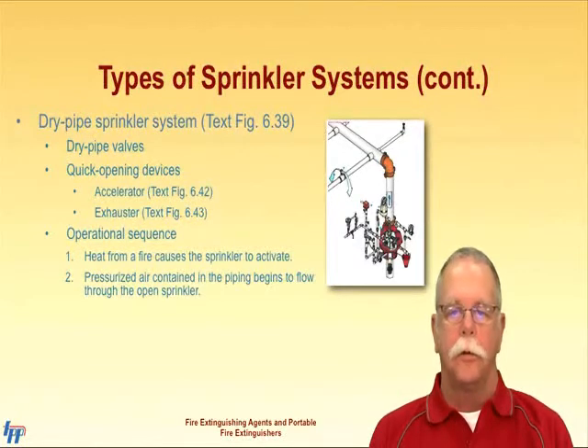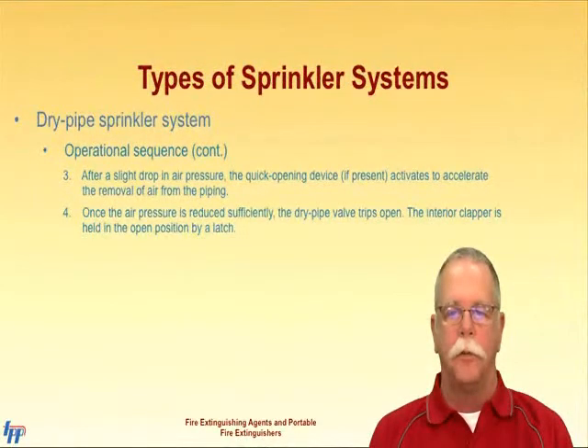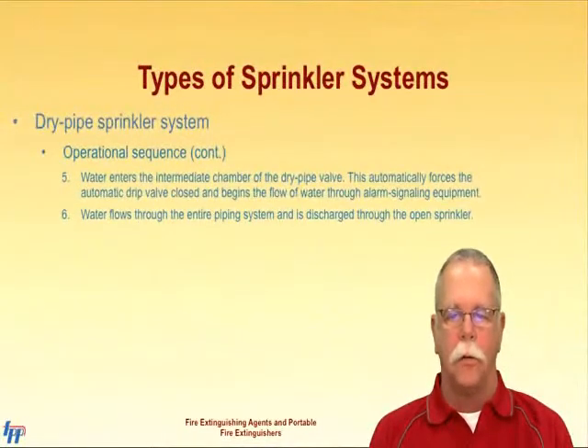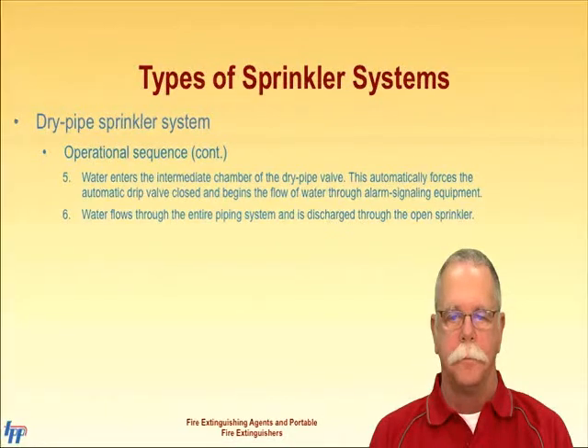Dry pipe systems are systems that have air or nitrogen under pressure, replacing water in the pipes exposed to freezing temperatures. When the sprinkler head is activated, the air escapes the piping, allowing water to enter the system at the dry pipe valve. The dry pipe valves prevent the water from entering the system using the air pressure in the lines. If the dry pipe system is large, a quick opening device will reduce the reaction time that the system needs to evacuate the air, delivering water sooner to the fire.